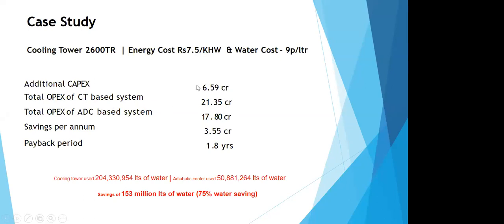So the extra cost that the client spent was recovered in less than 2 years. This saving of 3.55 crore majorly came through the water saving with respect to the cooling tower. If you look at the consumption, the cooling tower used almost 204 million liters of water, while the adiabatic cooler used only 50 million liters of water, saving almost 150 million liters, which is almost 75% saving of water. So this saving in water and the saving in electricity both resulted in the saving of 3.55 CR for the customer, and he spent almost 6.6 CR extra and recovered that extra cost in less than 2 years' time.